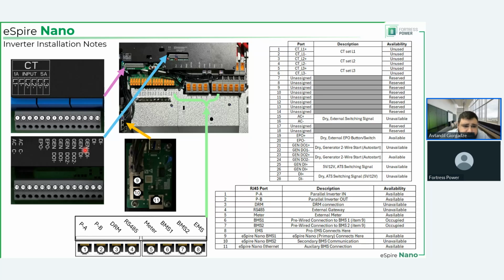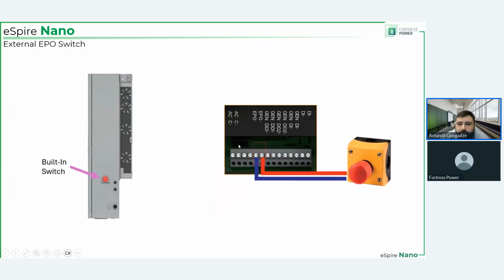Digital communication ports, only 2 pairs of them are used. EPO plus, EPO minus. So you connect your external emergency power off switch or a button here, and Gen DO2 plus and Gen DO2 minus, which I mean it's not really plus and minus, it's a dry contact for generator start, but you connect those cables right here for generator auto start. Everything else is not used, at least for now. And do I have time for one more slide? Yes, 2 more slides actually.